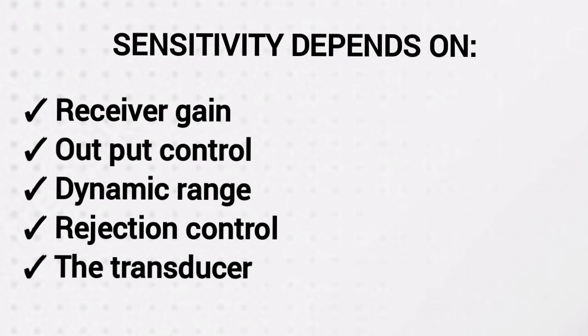Sensitivity depends on several parameters: the receiver gain, the output control, the dynamic range, the reject control, and the transducer. A transducer with good sensitivity requires less output power or receiver gain to display a weak echo. This sensitivity can be measured both with the AIUM test object and the TE phantom.